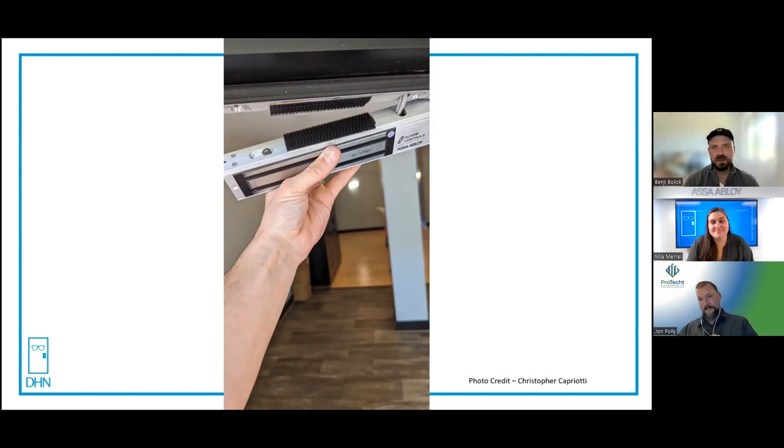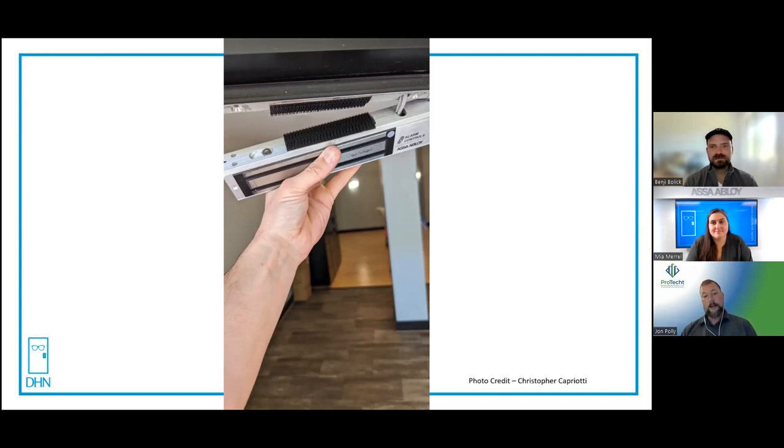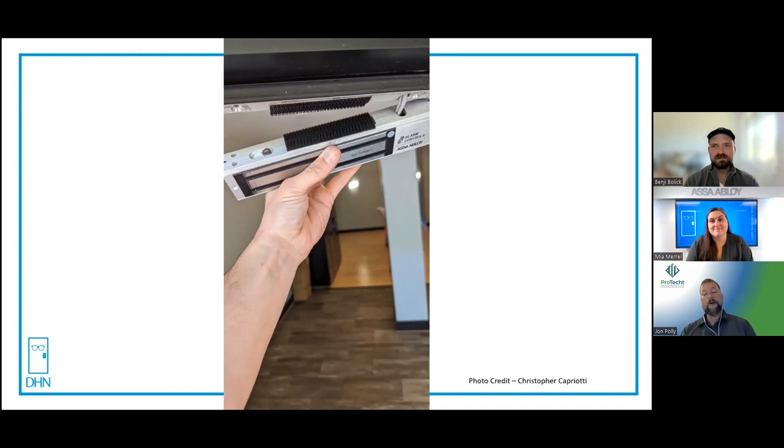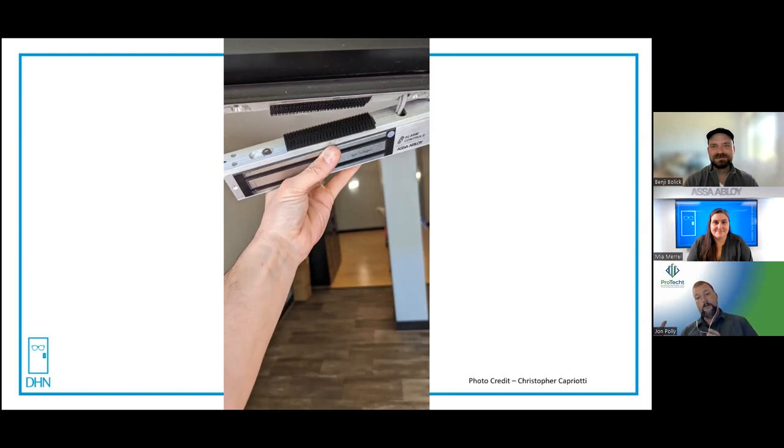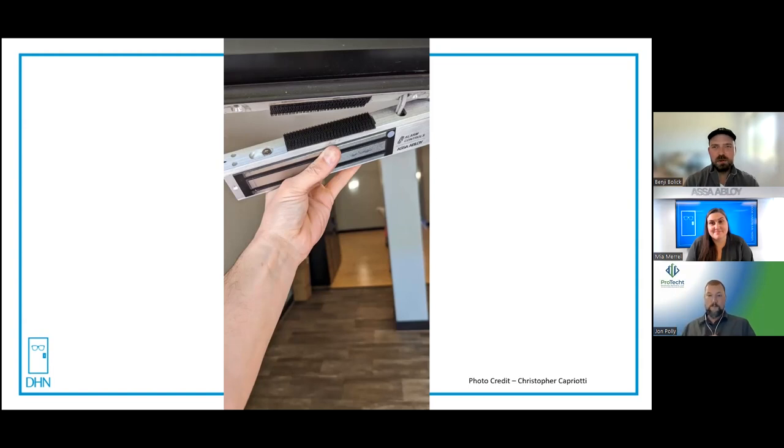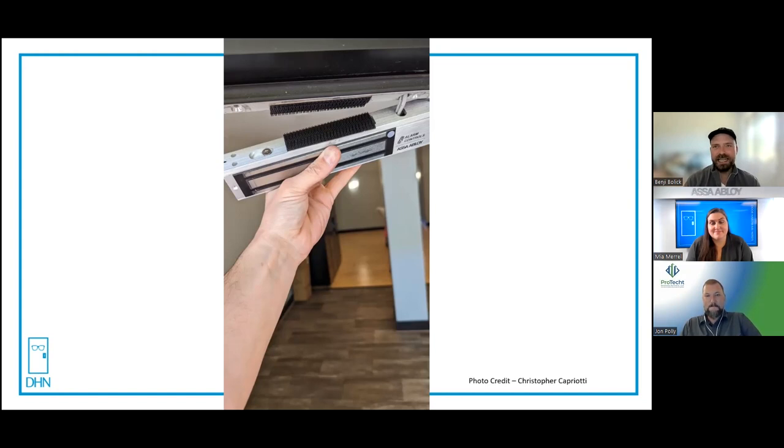I think it's hard to give this one a rating, but what do you think, John? Life safety-wise, I think you've got a problem because as soon as it energizes and hits an armature plate, it's going to pull the thing clear off, it's going to hit somebody in the head. Not knowing the rest of the install makes me question the rest of it. I would want an AHJ or somebody to look at the rest and make sure all the other code compliance pieces are there. From a technician level, you know better than this. I don't know that I would go a 10, but I'd see this falling and hitting somebody in the head with blood involved, so probably a seven or eight.